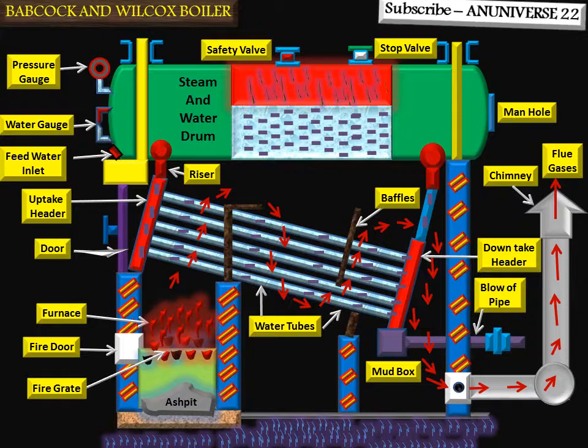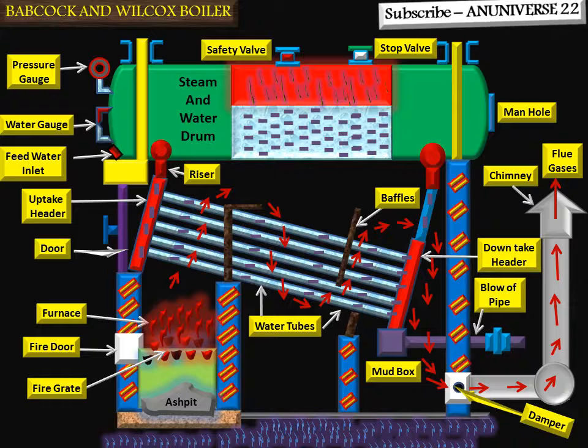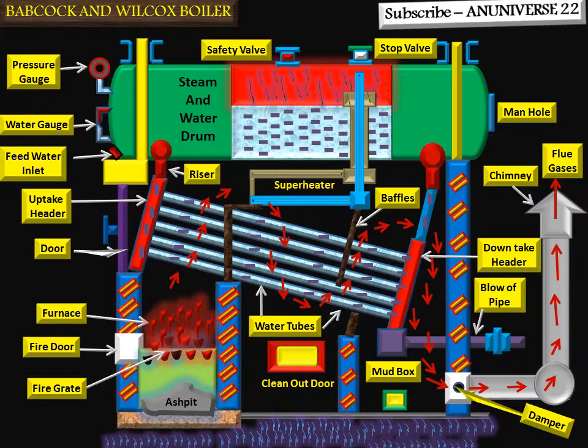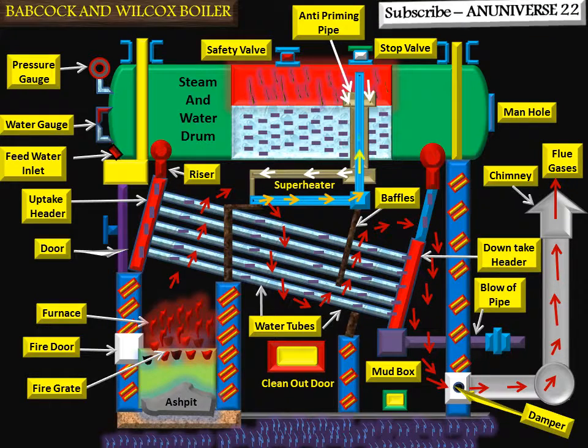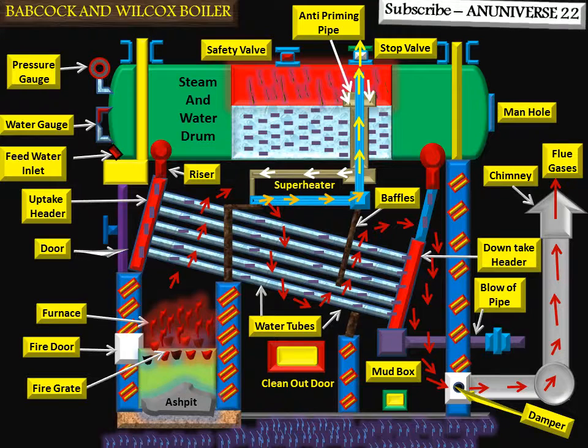A chimney is provided for the exit of gases and a damper is placed at the inlet of the chimney to regulate the draught. The superheater is situated on the upper side of the water tubes. One end of the superheater is connected to the drum and the other end is free for process work. Steam flows from the drum to the superheater where it is heated by flue gases and sent for process work.